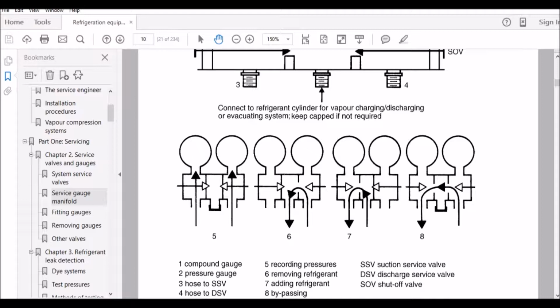As soon as I open the high side shut-off valve, any high side refrigerant that's coming from my high side gauge will enter into my service area and exit out of my yellow service gauge. The other way you can see is where we open the low side shut-off valve, with the high side closed. Again, what will happen is any refrigerant, in this case because the arrow is going this way, coming from my bottle, for example, will come from the bottle and enter into the blue hose line and into the actual system again.